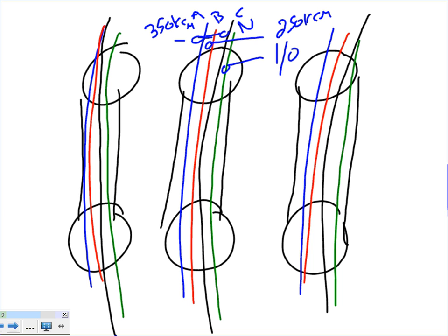Okay, so for the test, please do it this way: you got two 350s on A and C, and then 250 on B. 250 on B, A and C at 350, and the neutral is 1 aught. I'm not going to confuse you. I could do it differently slightly and make a smaller neutral.